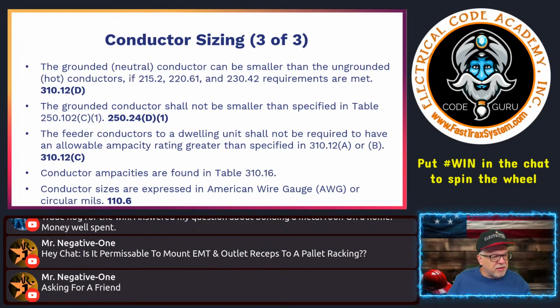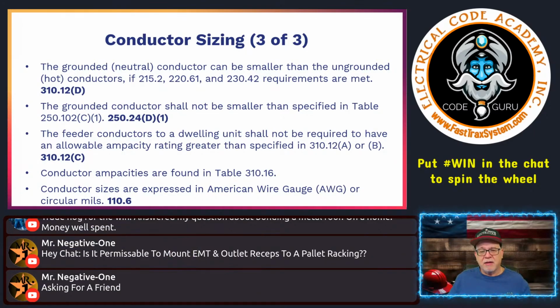What does he say here? Mr. Negative says, is it permissible to mount EMT or outlet receptacles to a pallet racking? You can't mount anything unless what you're mounting it to is designed to be able to support that load. So your best advice is to reach out to the manufacturer and see.